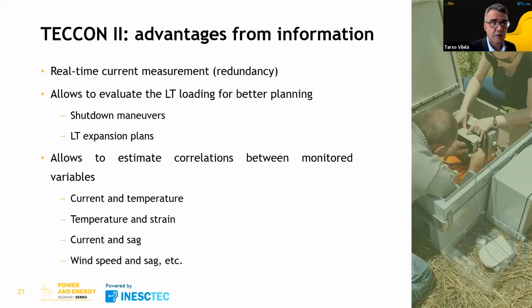Then we're going to list some advantages of the TECCON II system. We have a real-time current measurement, a redundancy in this measurement. It allows us to evaluate the transmission line loading for better planning of shutdowns and expansion plans. It allows us to estimate correlations between the monitored variables, which is something very rare. It's not common to have this opportunity to correlate 2 or 3 variables and check how the project is dimensioned, if it's okay or oversized. And next slide, please.